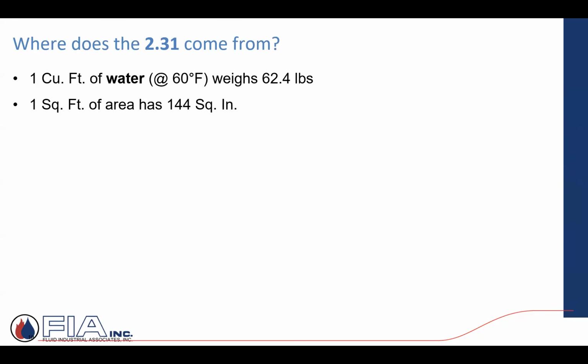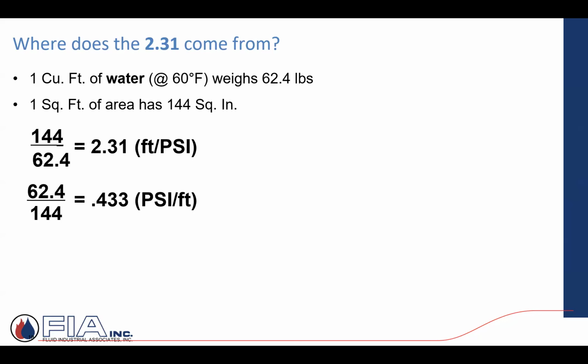Just real quickly, where does the 2.31 come from? So it's just saying, hey, 1 cubic foot of water at 60 degrees weighs 62.4 pounds. 1 square foot of area has 144 square inches. It's just doing math, playing a game back and forth. 144 divided by 62.4 is 2.31 feet per pound per square inch.